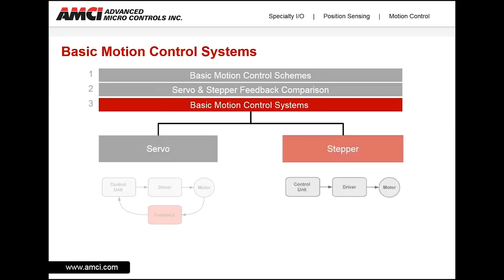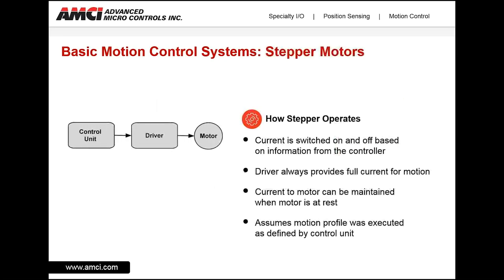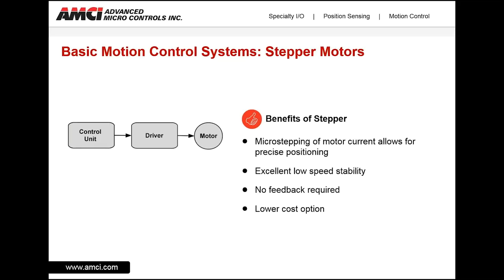Now let's take a look at a stepper. For a stepper system, current is switched on and off based on information from the controlling unit. The system runs as commanded with no adjustment based on any system feedback. Unlike a servo, the stepper drive outputs constant current through the move cycle. Because the stepper is a DC system, full current to the motor can be maintained at rest, eliminating the need for a holding brake. Benefits of a stepper system include: micro-stepping of the motor current allows for precise positioning, excellent low speed stability, and no feedback required, which provides a lower cost option compared to a servo.